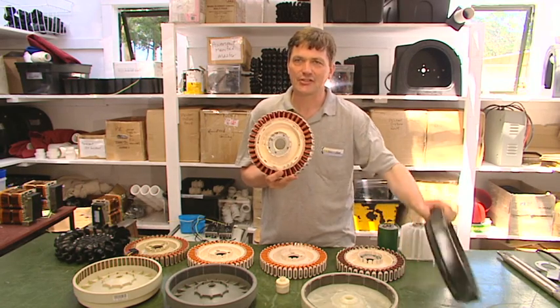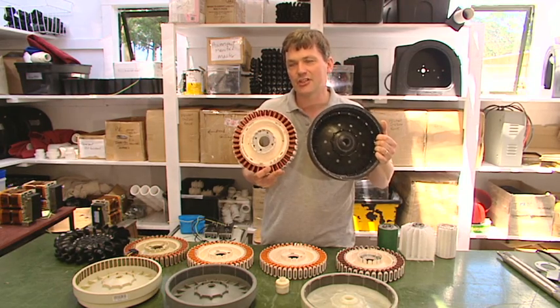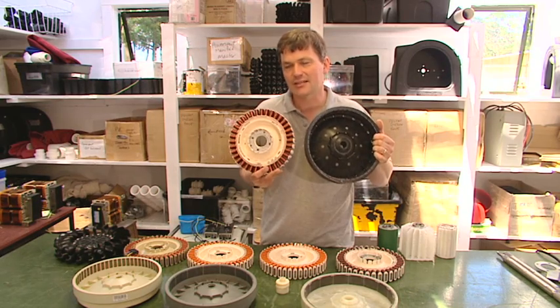So this is the combination that you're after. And with this combination you can make a hydro turbine that'll do a thousand watts at a thousand rpm.